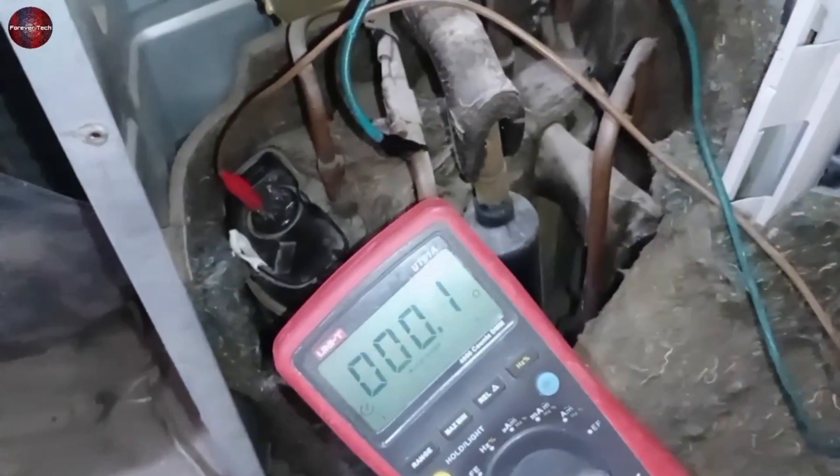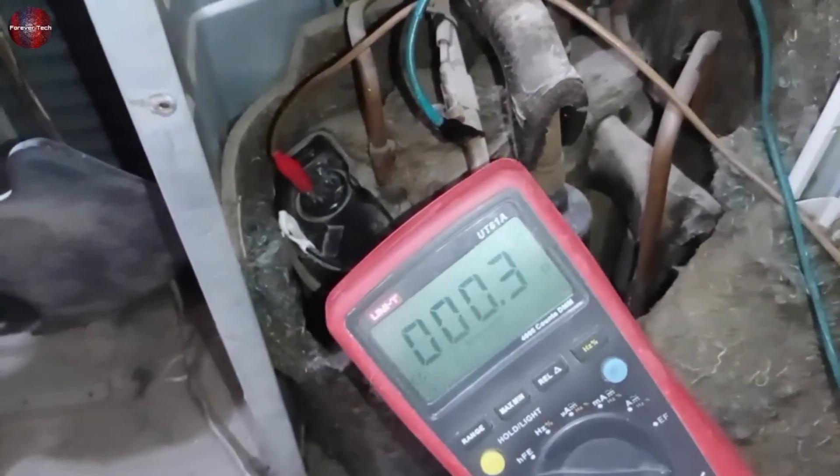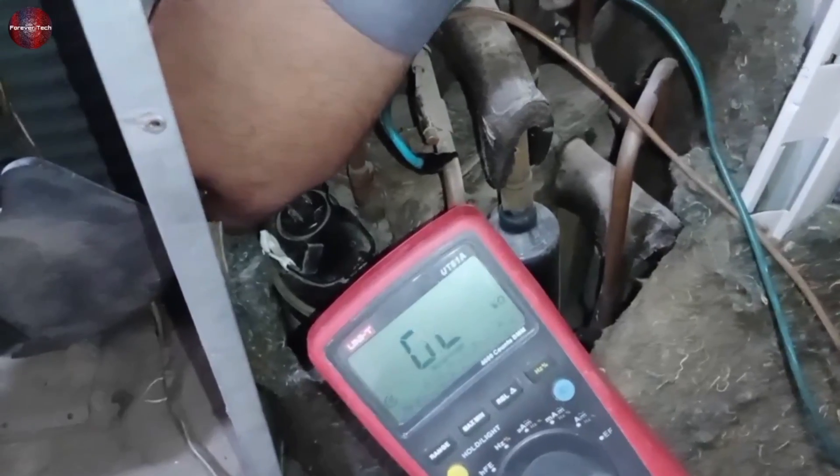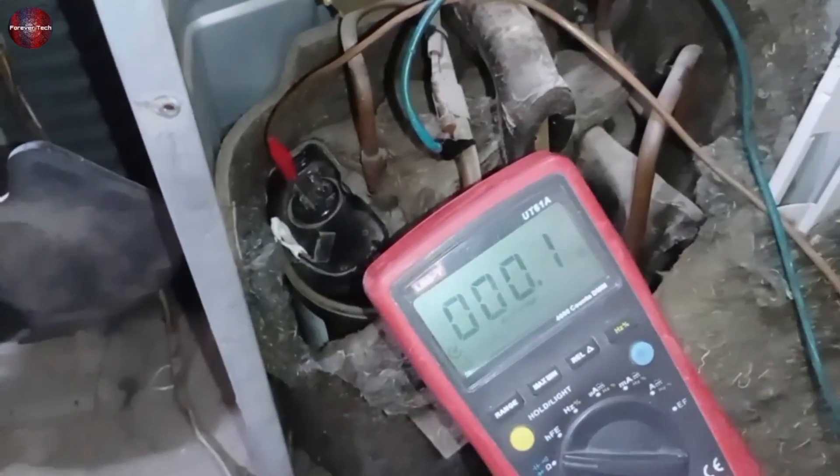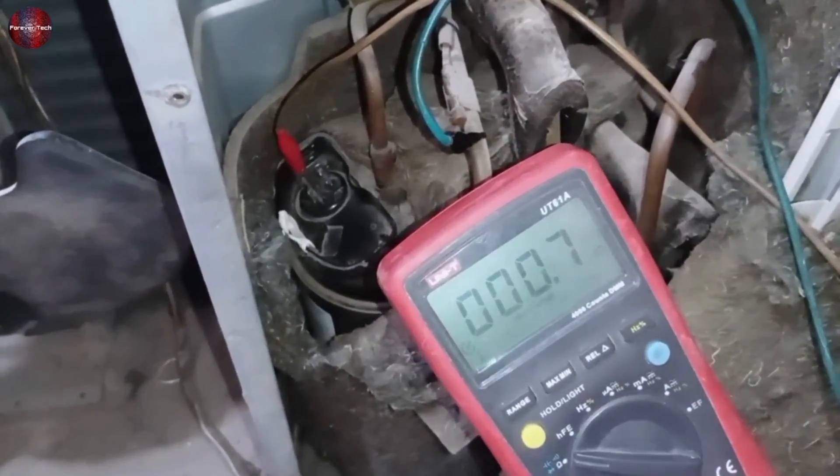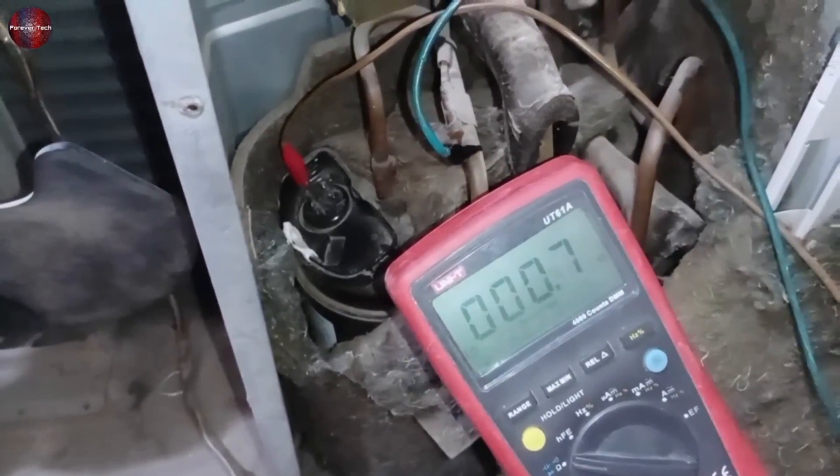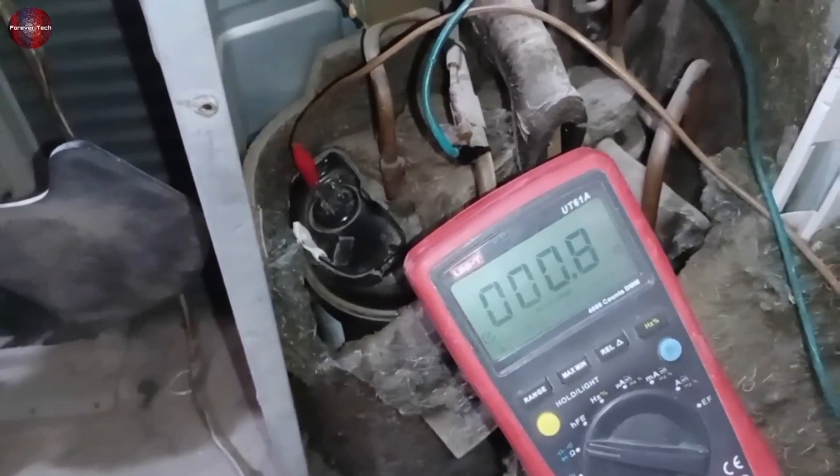Now I will remove the probe from the terminal we checked to the next one. Still, the body short is present. If you check it on one terminal, you will know the short of the compressor, but I will also show you the last terminal. See, it is the same on this one as well.